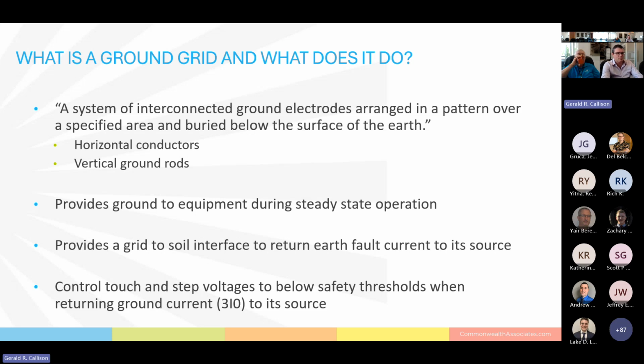Well, basically a ground grid does two large functions. During steady state operation, it provides a source of ground. Your dead tank circuit breakers are dead tanks because they are grounded. Their grounding is connected through leads to the station's ground grid, and that provides grounding during normal operations.